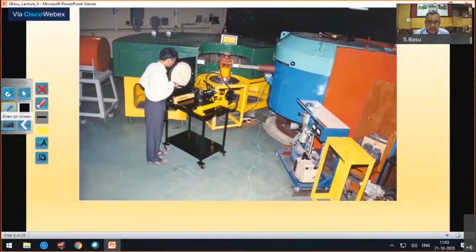This is the monochromator drum, which is a common feature for most of our instruments, and what you see is a number of neutron detectors, position sensitive detectors, which are sitting here. In this particular case, it has a wide range of angle, and the sample sits here. This is a sample table. Now, why a wider range of angle compared to diffraction? Let's probe that a little bit more.